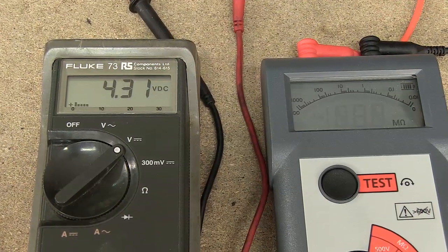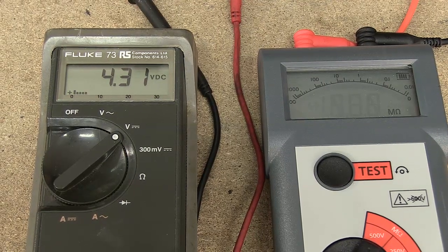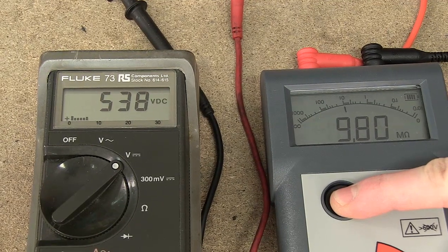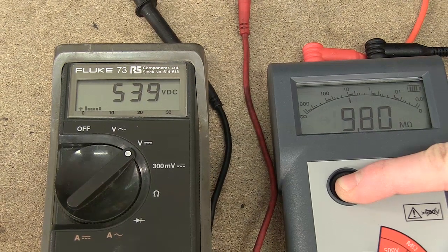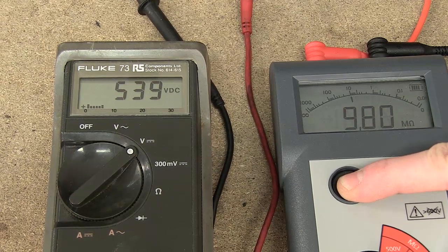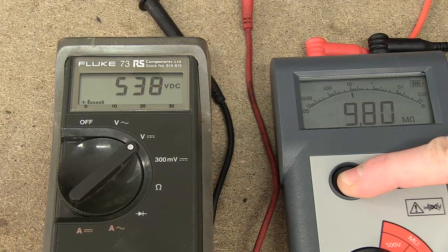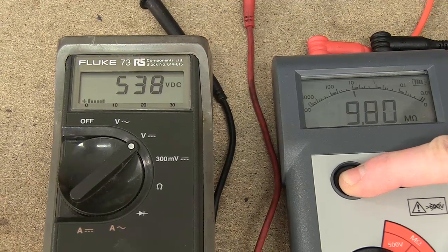Unlike a normal multimeter, insulation testers use a much higher voltage to test for a resistance leak. If I press the test button here, you can see that the meter attached to the megger is giving a reading of well over 500 volts, whereas a multimeter would typically use 9 volts to measure. Therefore a megger is more likely to show a failing element that is tripping the fuse board.